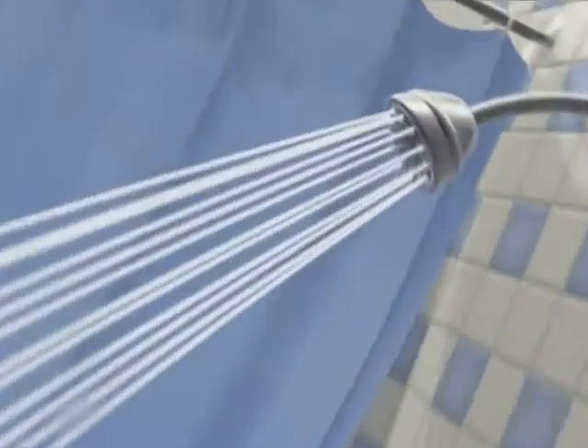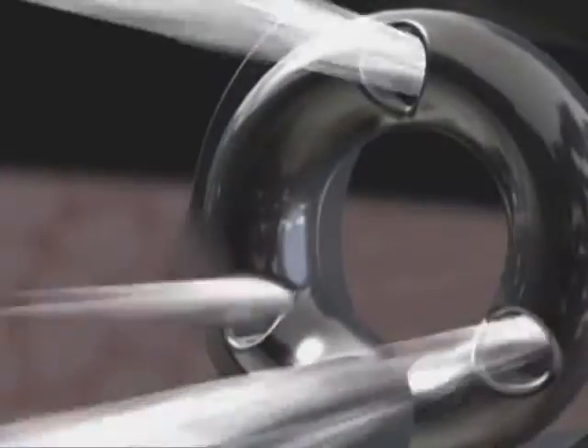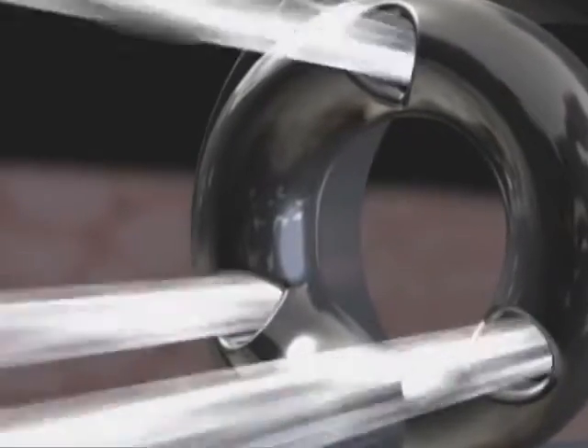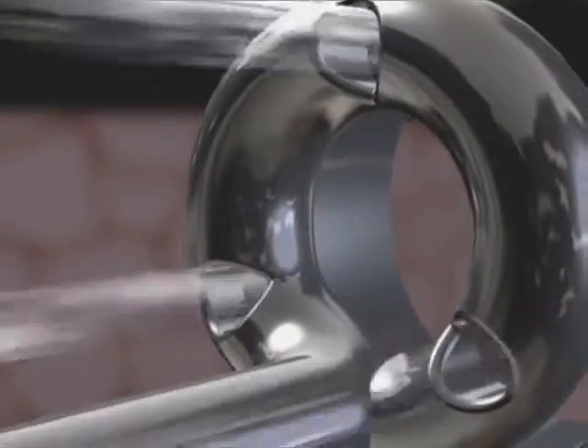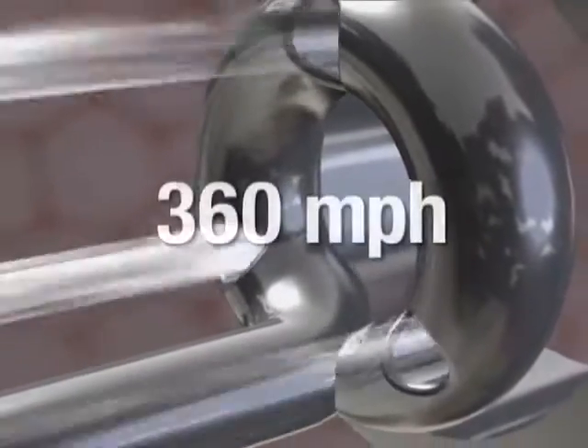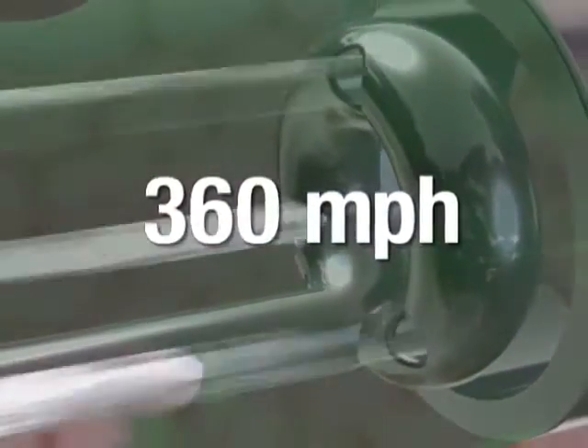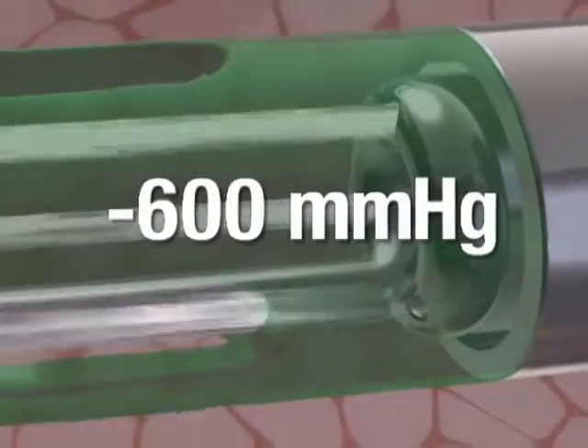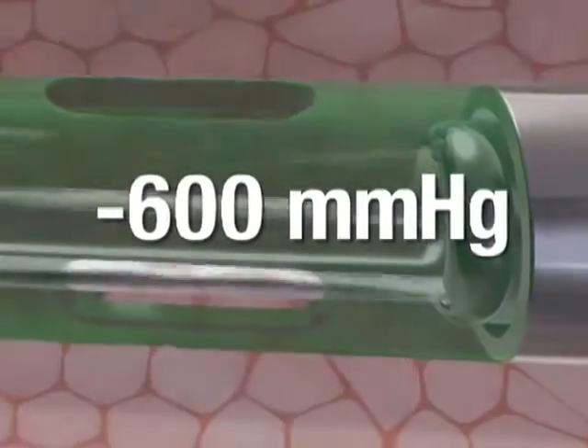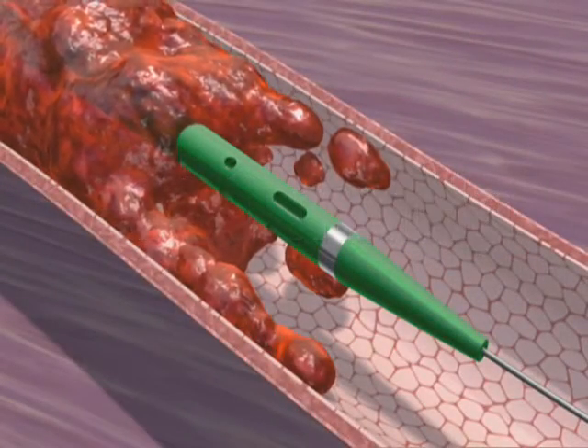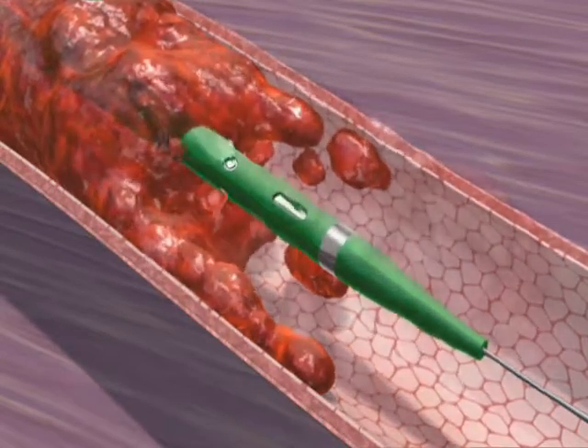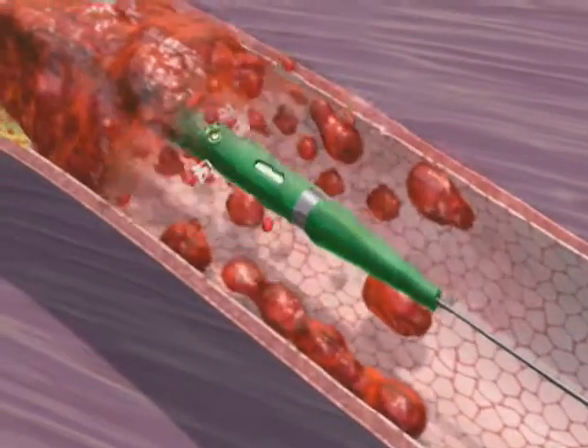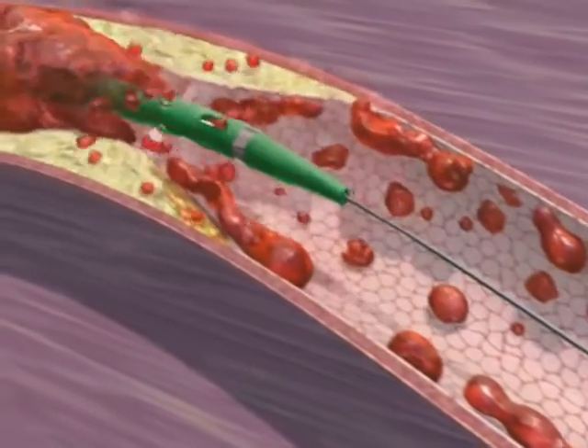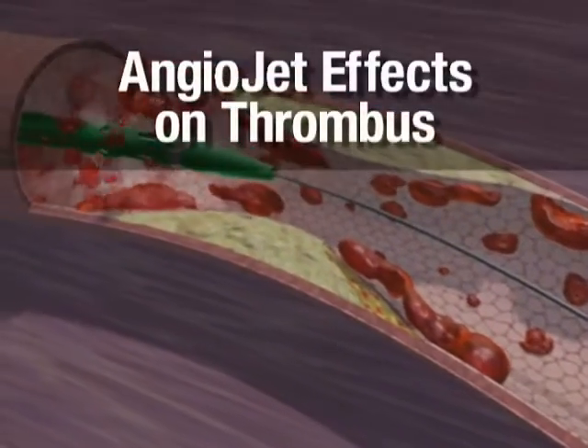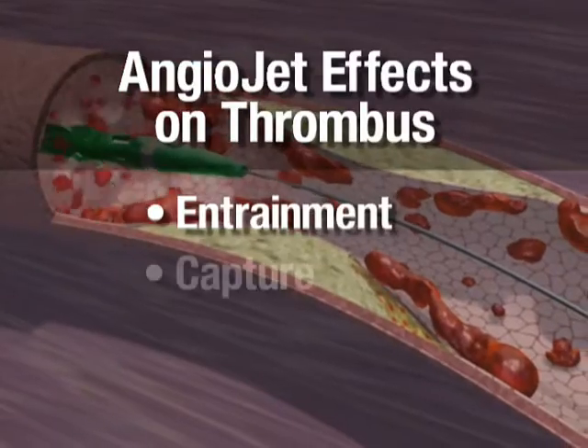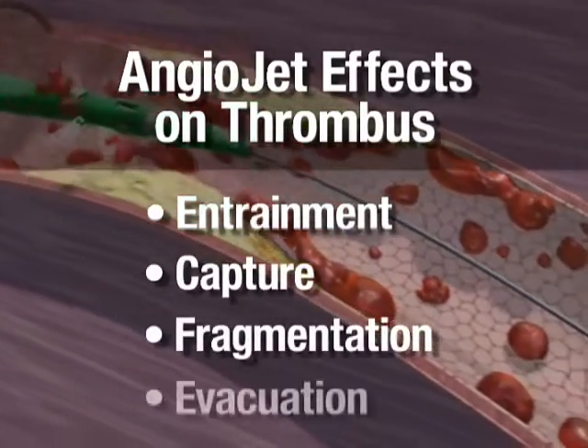AngioJet utilizes high-velocity saline jets to generate very strong negative pressures. Saline is pumped to the catheter tip, where the jets are directed backwards at a rate of 360 miles per hour, reducing local pressure to less than negative 600 millimeters of mercury, a near-perfect vacuum. These powerful vacuum forces, in combination with AngioJet's cross-stream technology, allow it to efficiently extract thrombus through a combination of four effects: entrainment, capture, fragmentation, and evacuation.